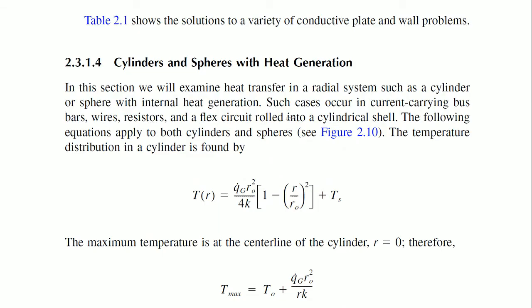Internal heat generation occurs in current-carrying bus bars, wires, resistors, and flex circuits rolled into a cylindrical shell. For example, you have wires and resistors. If you have a copper conducting wire in concealed wiring inside a building, the copper has a simple PVC coating. When you bring it outside, the same wire can carry a higher current — first because you have convection, and second because it is not looped and confined.